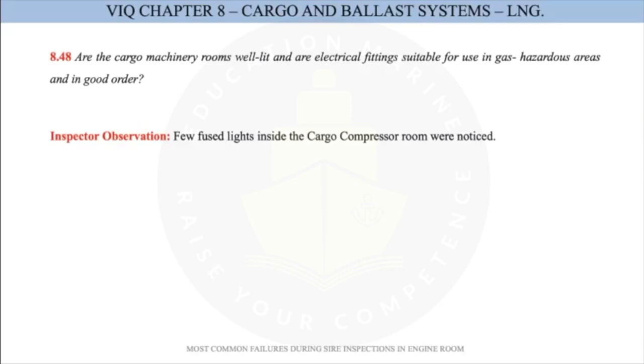They don't have any cracks or broken glass parts, anything like that, because this could be even more dangerous, and of course bigger observation, because they have to be sealed and there should be no entrance for the gas in case to come inside the fixture, because normally you have a limit switch. When you open it, it's fused off. Yeah, it's without power, and then you can replace lights, and then you put it back to check. This is normal. But if this cover is broken, it's within observation for sure.